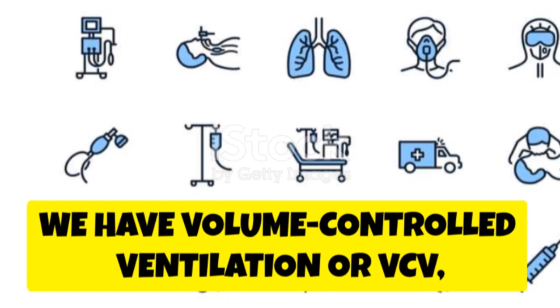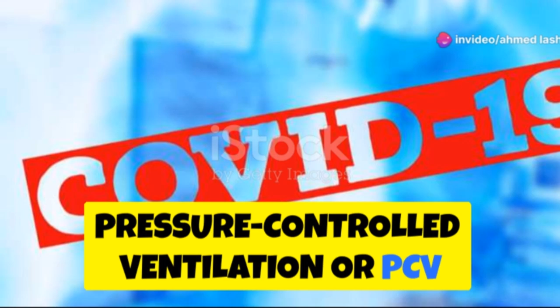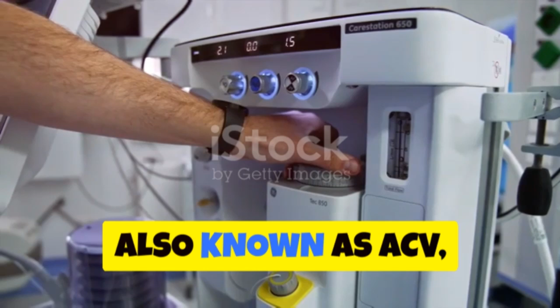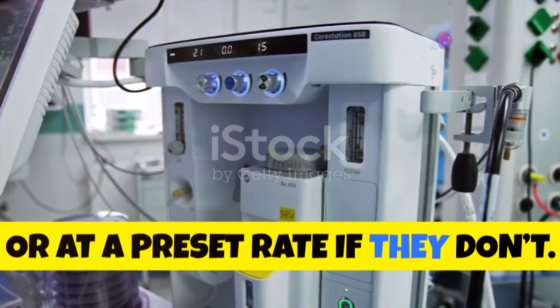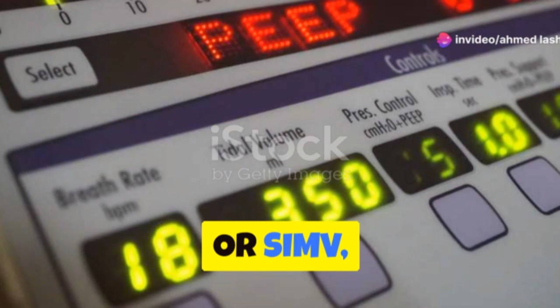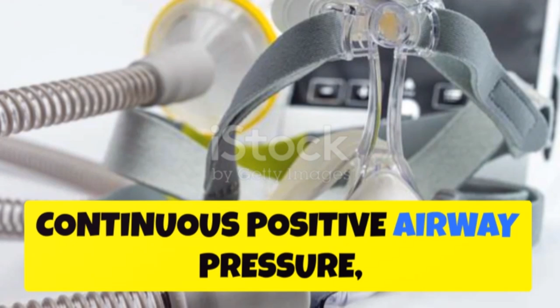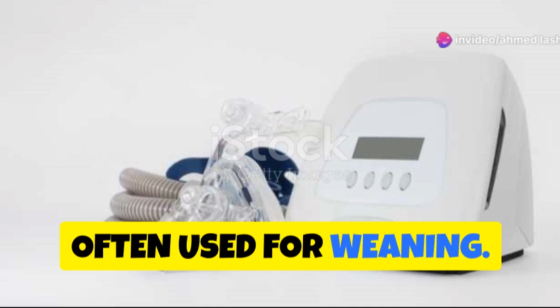Alright, moving on to the modes of mechanical ventilation. We have volume-controlled ventilation, or VCV, which delivers a preset tidal volume. Pressure-controlled ventilation, or PCV, delivers air until a preset pressure is reached. Assist-controlled ventilation, also known as ACV, provides a breath every time the patient initiates one, or at a preset rate if they don't. There's also Synchronized Intermittent Mandatory Ventilation, or SIMV, which allows spontaneous breathing between preset breaths. And finally, Continuous Positive Airway Pressure, or CPAP, keeps airways open with constant pressure, often used for weaning.